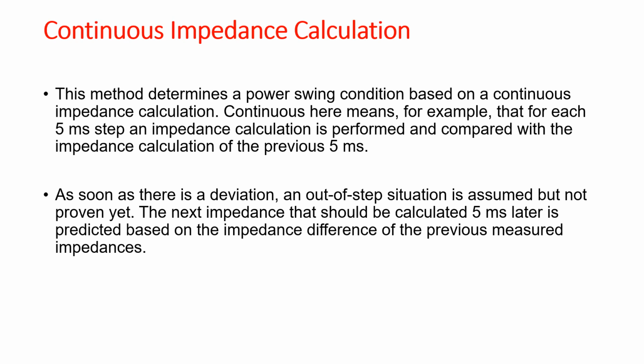The rate of change of y and x, or say x and r, is measured after every 5 ms interval, and that delta, if it changes rapidly from the first to the second, the third, they are compared with each other, and if the rate of change of the delta, or the m value or the k value, that is the tangent of the angle, is very rapid. It is not delta, that is the rotor angle, it is the angle of the x and r here.